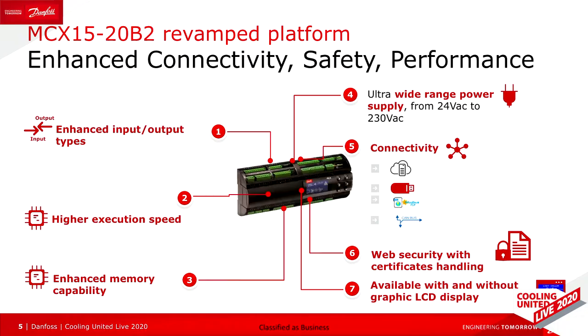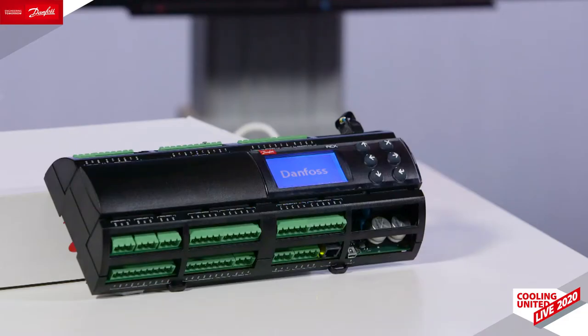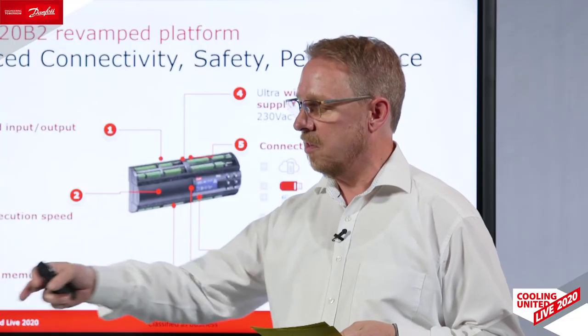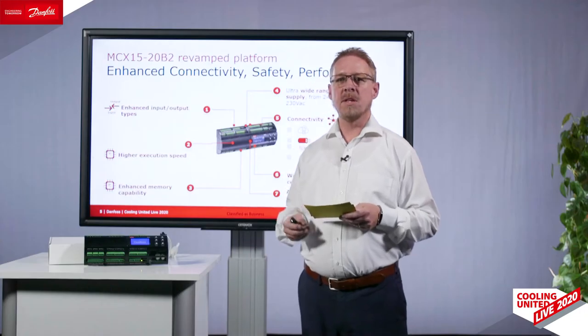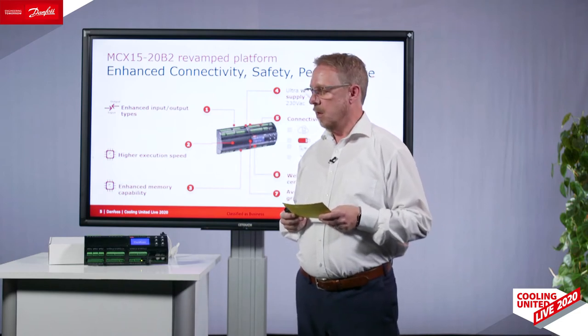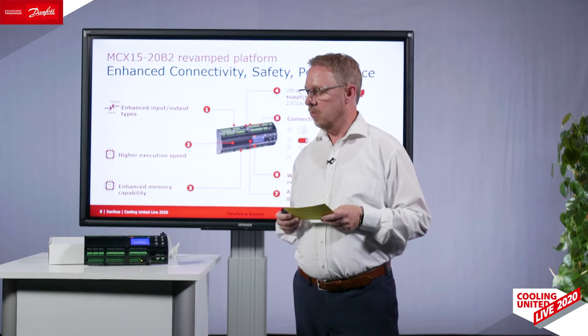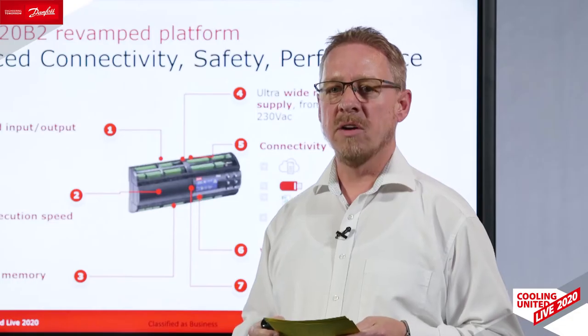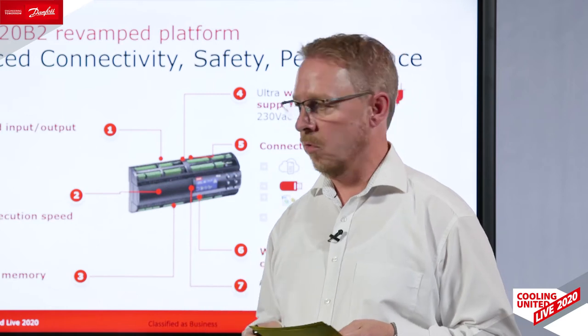We also have two RS485 serial lines where you can communicate to field devices like inverter compressors, Turbocor compressors, or other field devices like fans and energy meters. With the second line, you can transmit data to a building management system. We also have a CANBUS interface to communicate between controllers in a large network and exchange data very fast.